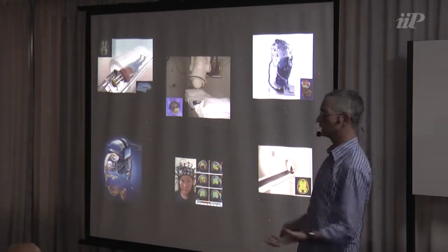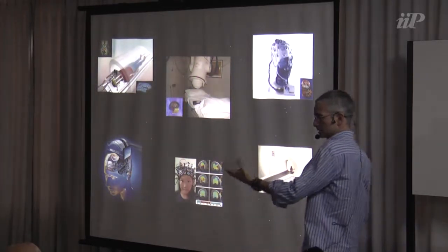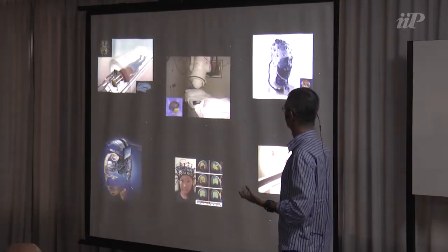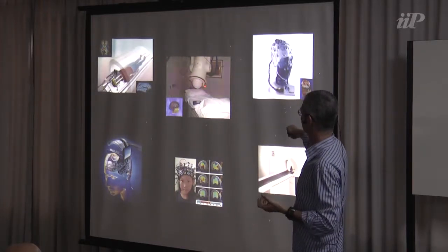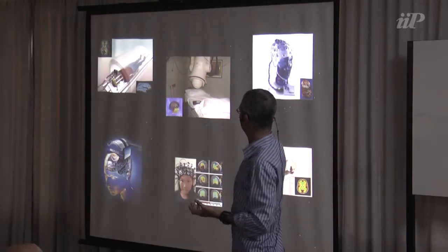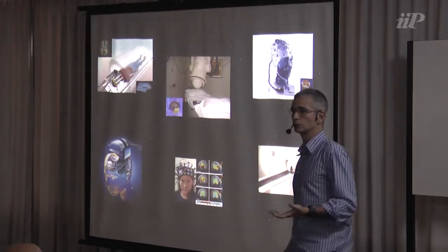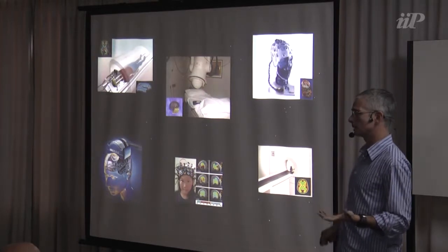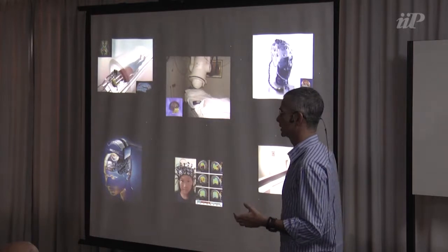So you cool down these SQUIDs, and then you're capable of having this system detect that activity, that magnetic field. The other problem is that these magnetic fields are very weak, and as the detectors are very sensitive, this whole system needs to be inside a magnetically shielded room, which is expensive. To buy a system like this one, you would spend something around $2 million to $2.5 million, the whole system.